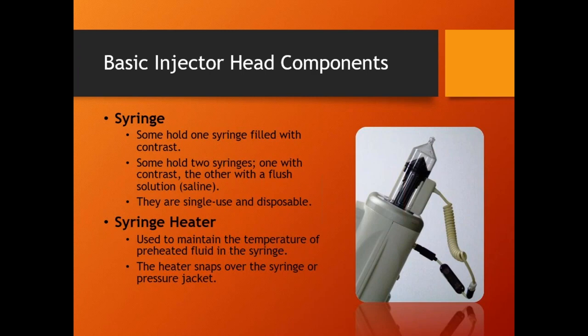Yes. Now, this is almost universally true as well. The syringes are model specific. There's a couple of examples, and it's only because this model replaced this model, but they didn't change the syringe. That's the only time there are exceptions. But the syringes on that Stellant only fit the Stellant. They don't fit any other model. That's true with pretty much every single model. Every single contrast injector system has a syringe specifically for it. You can't just run out of the room and just give me a syringe. No, it matters. And they are one-time use only for medical use. One-time use only. They use it once and throw it away.